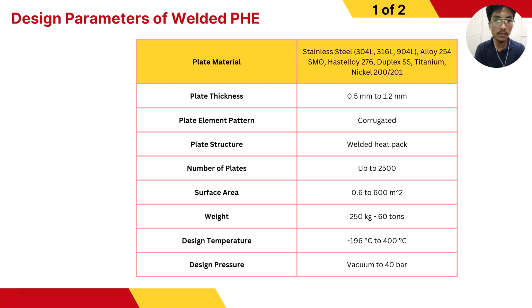So the design temperature can range from negative 196 degrees Celsius to 400 degrees Celsius. So it is according to Hoffman exchanger or HFM industry. So it is varying from negative 196 to 400 degrees Celsius, but it also depends on the manufacturers of welded plate heat exchangers. Some heat exchangers can be utilized up to 350 degrees Celsius, 380 degrees Celsius, and so on.